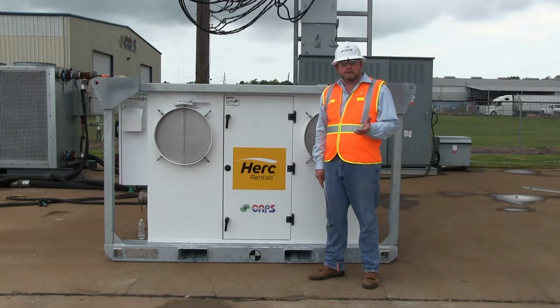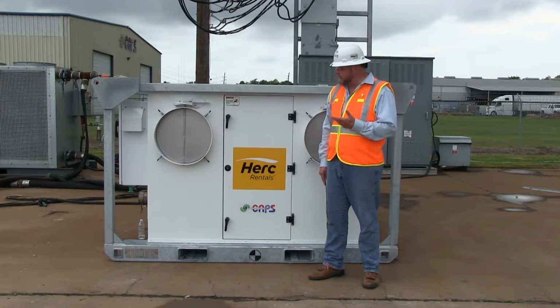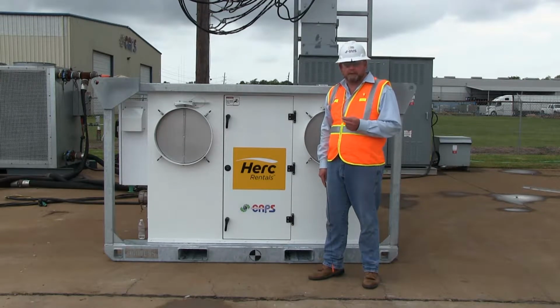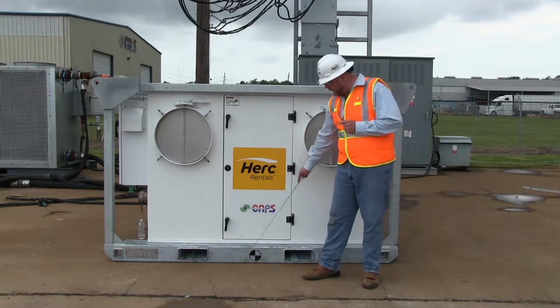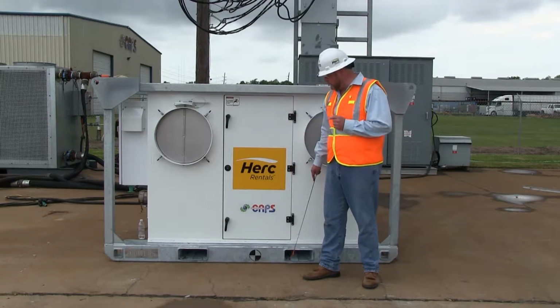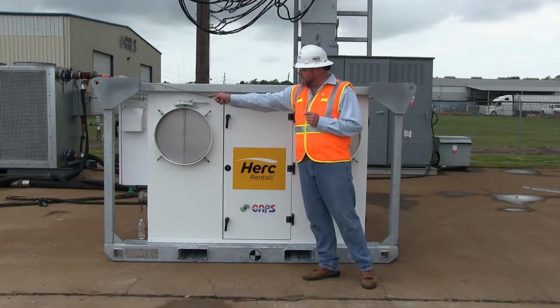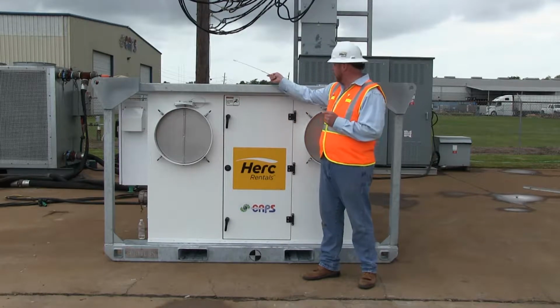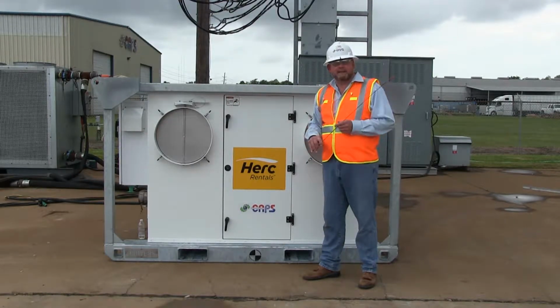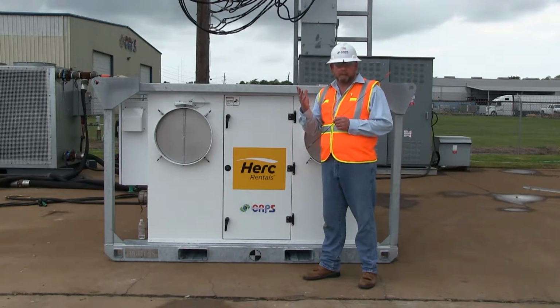The next step in our setup is to determine how we're going to move the unit. The 50-ton chilled water air handler comes with two methods. The first is the forklift pockets here at the base of the skid. The second is overhead lifting points. There's one in each corner. The unit can be lifted by a single point from a crane or cherry picker.